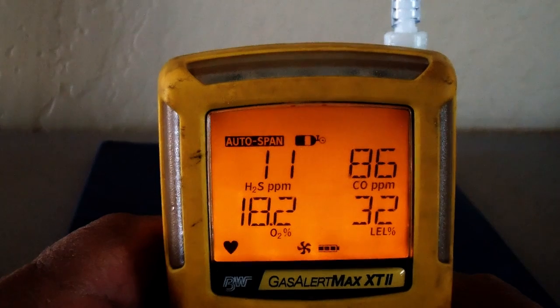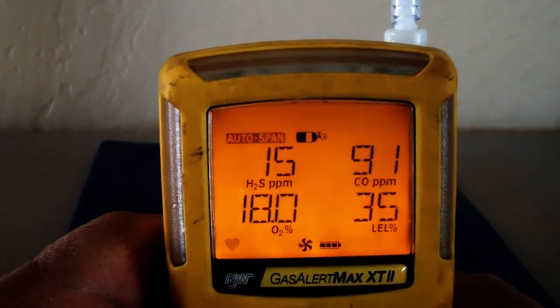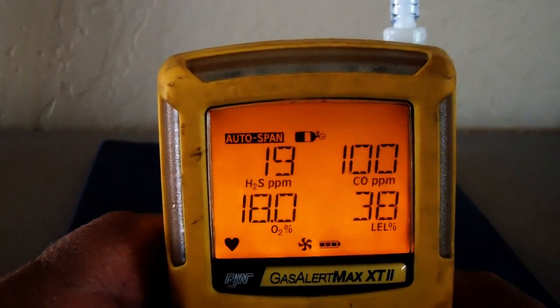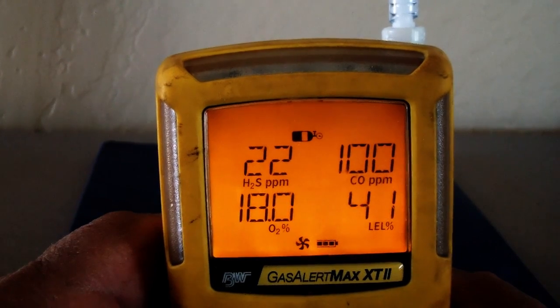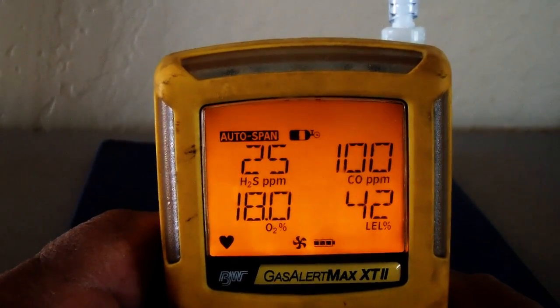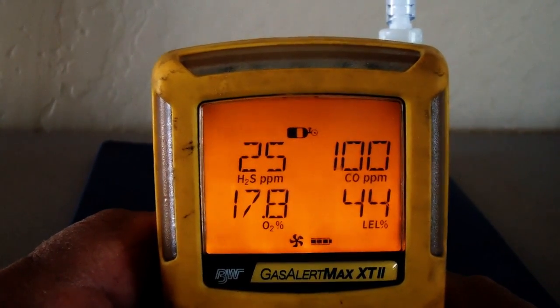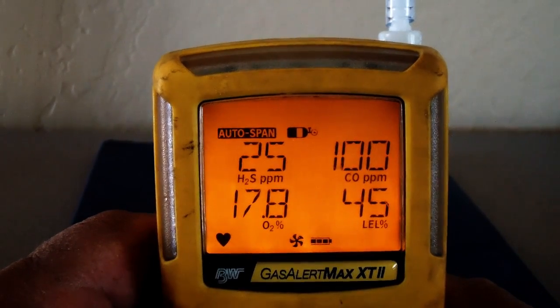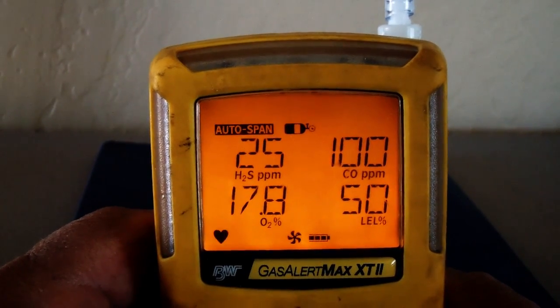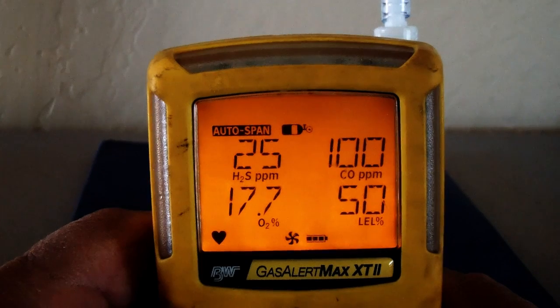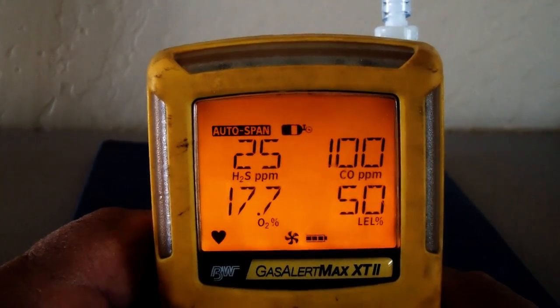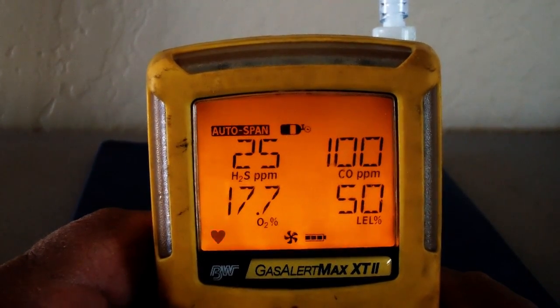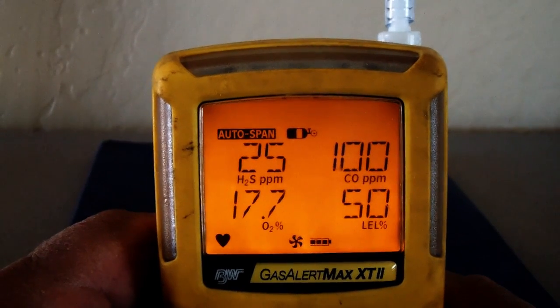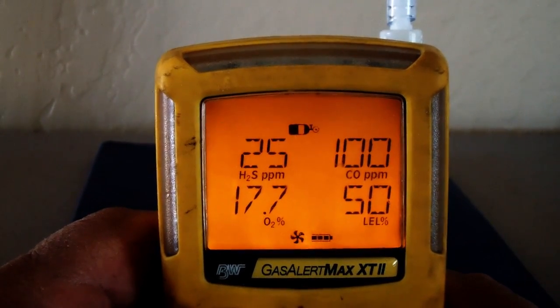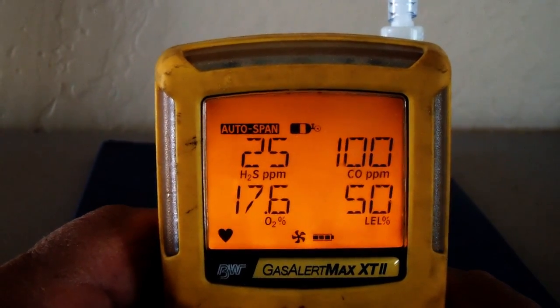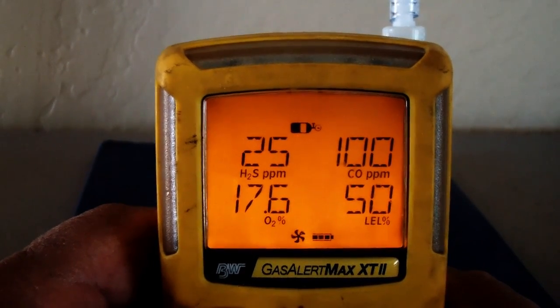And we talked about the values on the cylinder in our previous video. We're just waiting for this meter to settle into those values. And unfortunately, I can't unplug it. It's got to go through the whole phase of calibration, so it takes a little bit longer, which requires a little more cal gas, which requires a little more money, but it is what it is.